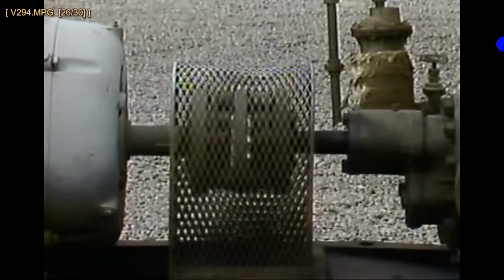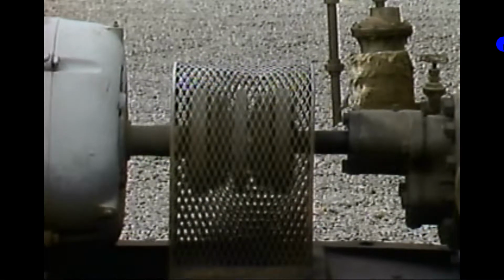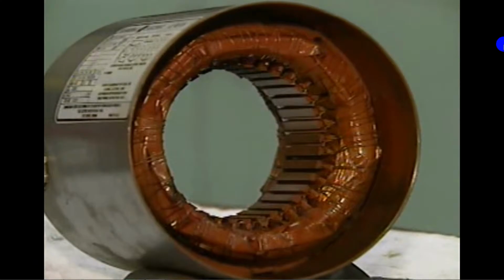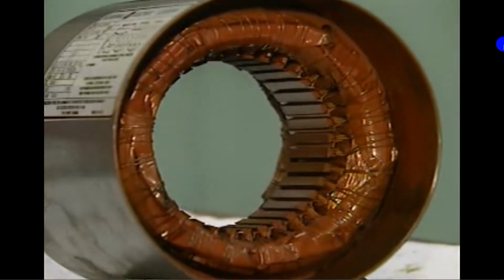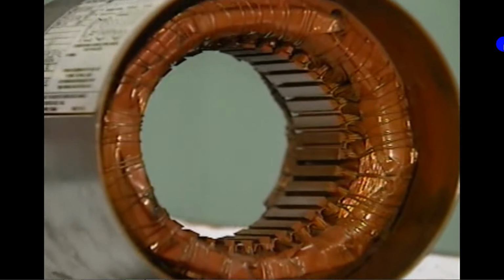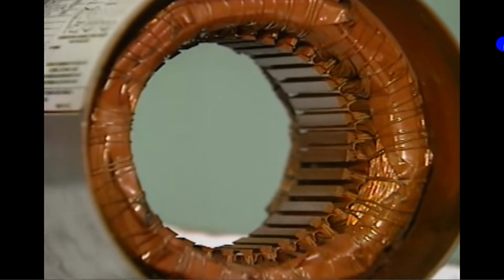When a typical AC motor is first started, current is 3 to 5 times higher than the motor's normal operating current. This surge of current could trip the power supply and in some cases may damage the motor's windings or the cables leading to the motor.